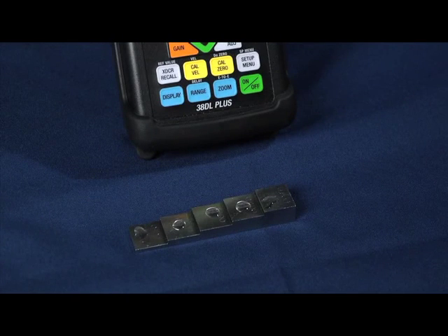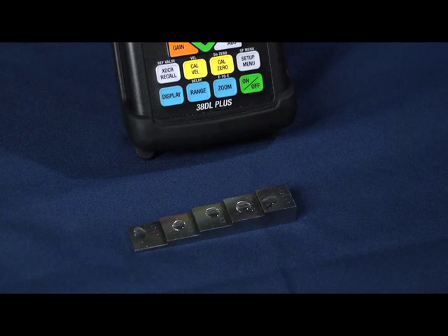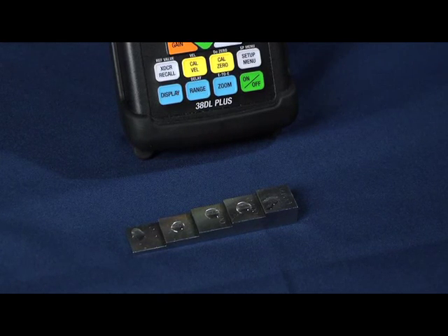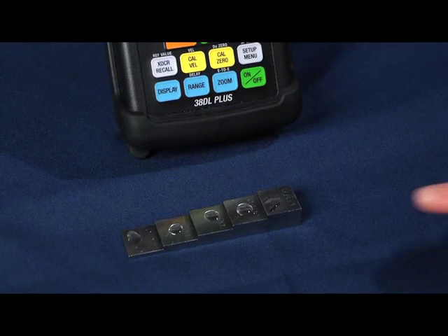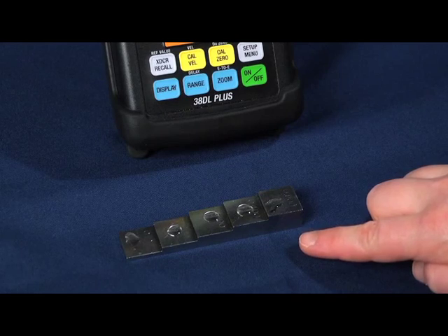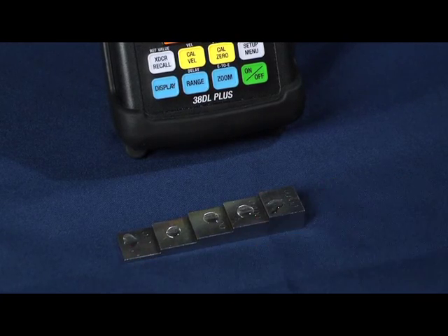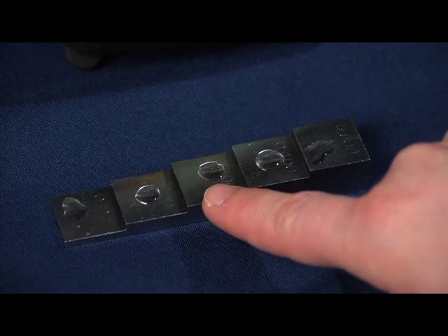At this point, we are ready to perform a two-point calibration. In this example, we are going to be calibrating to a five-step carbon steel test block, where the maximum thickness is five hundred thousandths and the minimum thickness is a hundred thousandths, with a hundred thousandths steps in between.